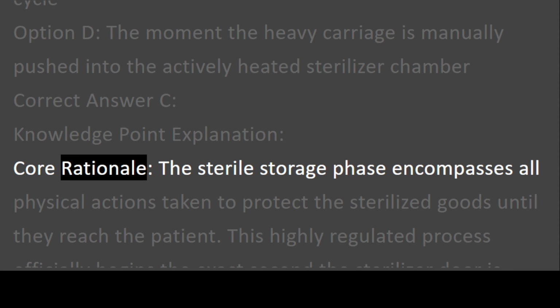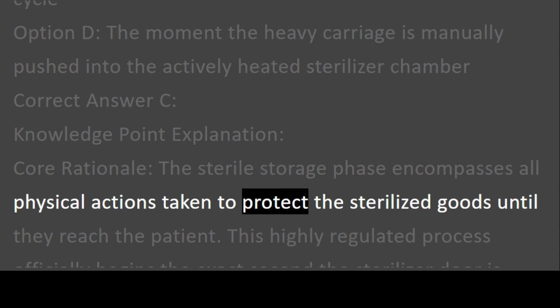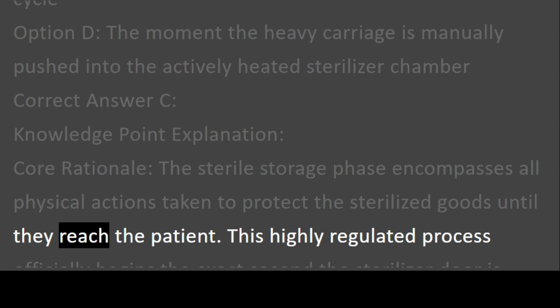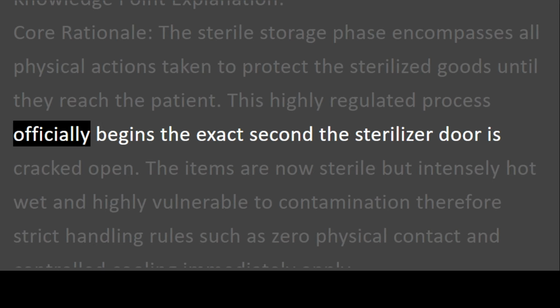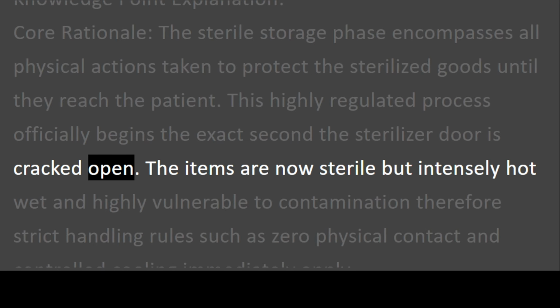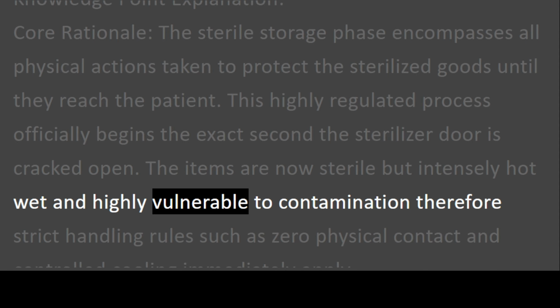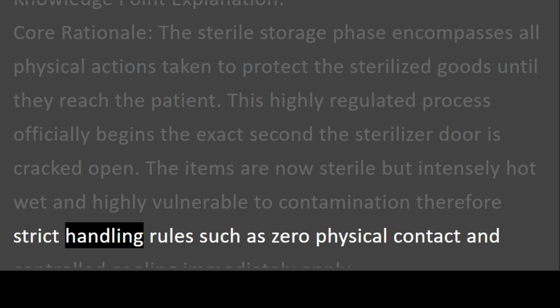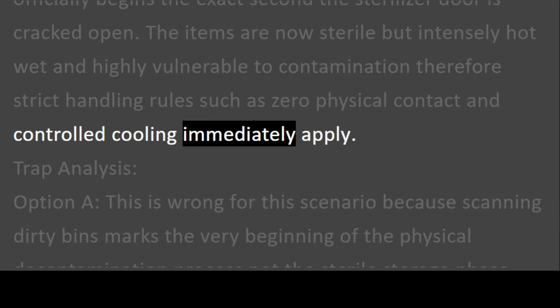Knowledge point explanation. Core rationale. The sterile storage phase encompasses all physical actions taken to protect the sterilized goods until they reach the patient. This highly regulated process officially begins the exact second the sterilizer door is cracked open. The items are now sterile but intensely hot, wet, and highly vulnerable to contamination. Therefore, strict handling rules such as zero physical contact and controlled cooling immediately apply.